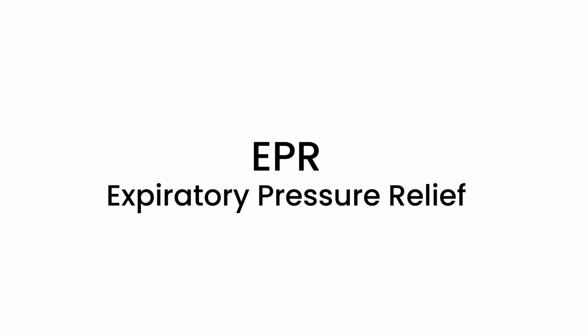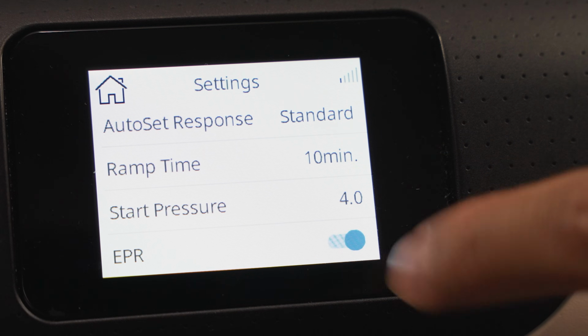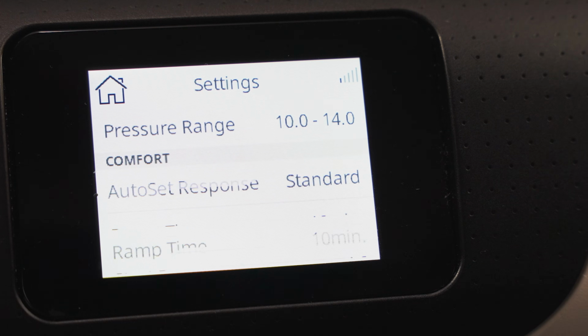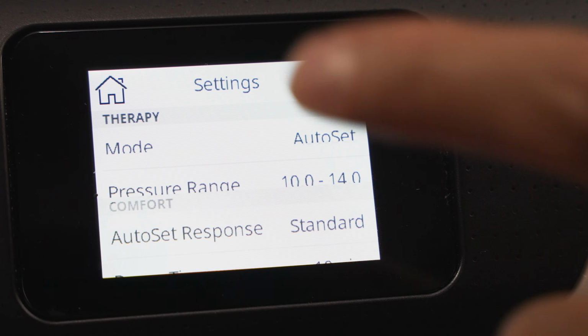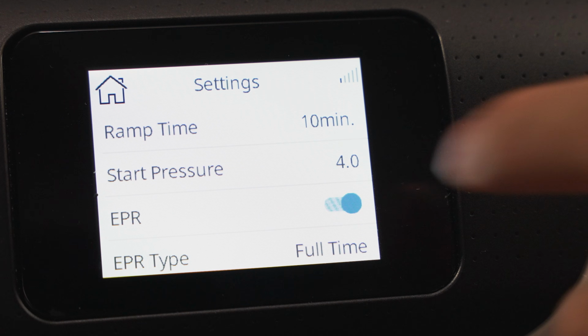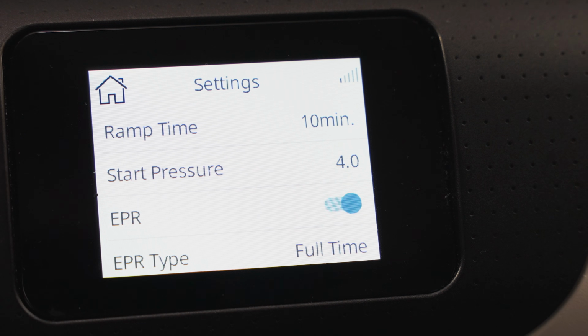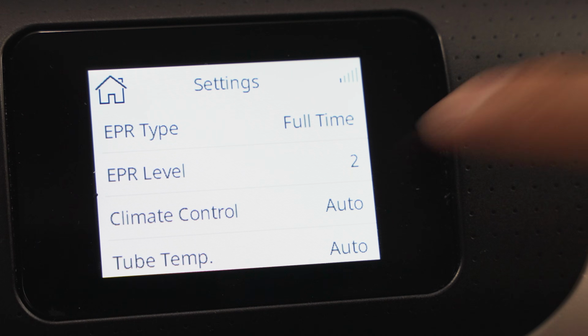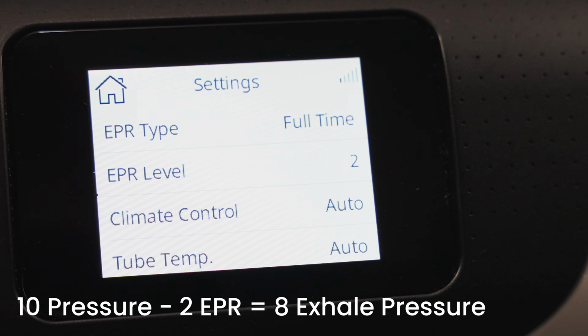Okay, now let's go to EPR. EPR is a comfort setting, so you can turn it on and off like that. If you turn it off here, your pressure is always going to be 10 to 14. But if you turn it on, it's going to decrease the expiratory pressure below what you had it set at. So for example, if you have an EPR of 2, then at a 10 pressure, it's going to give you a 10 pressure on your inhale and an 8 pressure on your exhale, which means it's going to be a little more comfortable to exhale. Why? Because 10 minus 2 equals 8, okay?